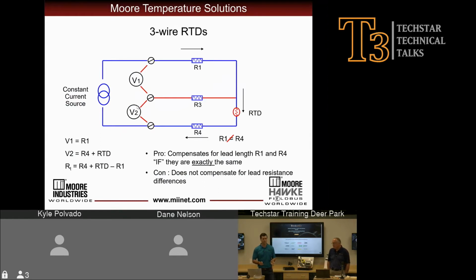But Murphy's law tells us that that's never going to happen. They're always going to have some differences, and there's always going to be a little bit more corrosion on one wire than there will be on another wire. And so with that, we know that R1 and R4 will never be exactly equal. And since they aren't equal, and we're including R4 plus RTD minus R1, we're not going to get an accurate temperature measurement because we're including that resistance in the lead leg and trying to subtract an amount that doesn't equate to the amount that we're adding into our measurement.